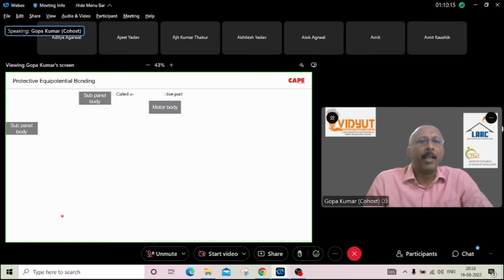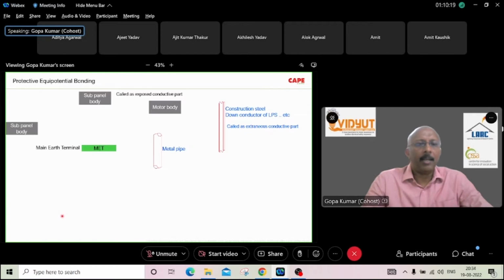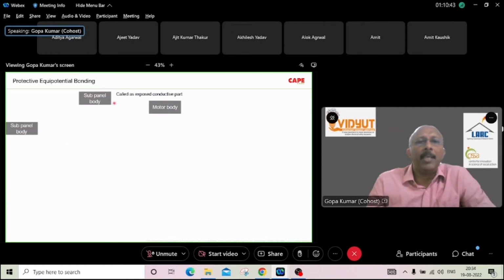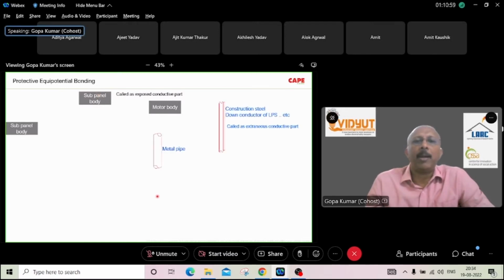The second point, protective equipotential bonding. In every electrical installation, fault protection is achieved by protective equipotential bonding and automatic disconnection of supply. What does it mean? It means every metallic object in your electrical installation must be interconnected. Say, for example, your building has exposed conductive parts, like a motor or the sub panel, where the current carrying objects are inside. The electrical equipment has a body, and whenever there is a fault inside, a person can get electrocuted. So you have the exposed conductive part. You also have extraneous conductive parts like the metal pipe, the aluminum frame of a glass facade, or the rebar of your building.